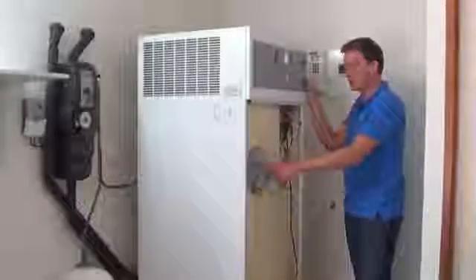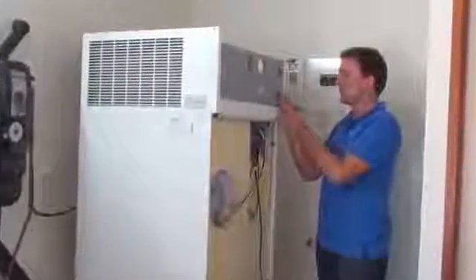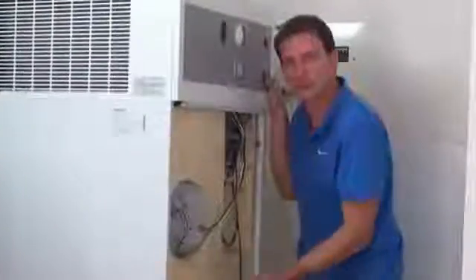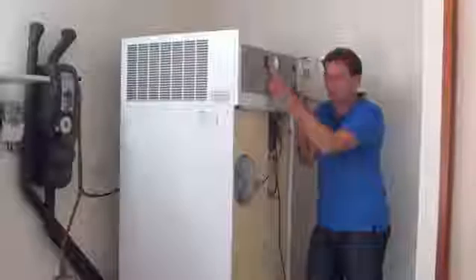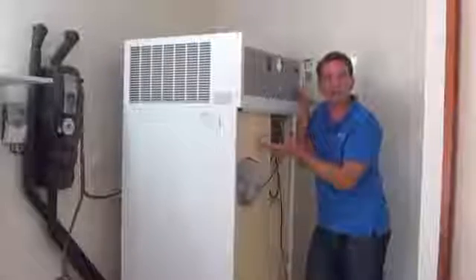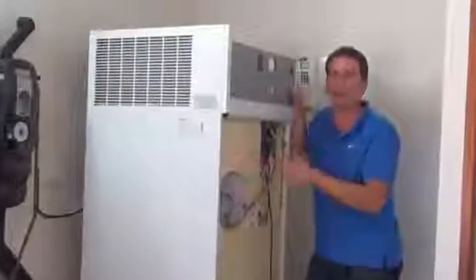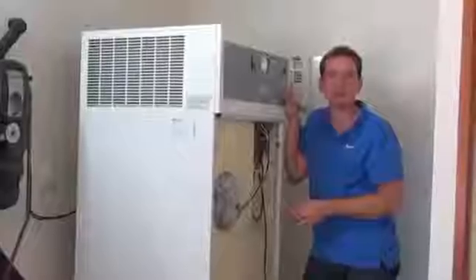Alright, just to show you quickly some other features that this heat pump has. Here we've got a switch that pushes the water in the tank up to 60 degrees. It actually switches on an electric element over here. We push the water above the normal 55 degrees that the heat pump generates. By doing that, you kill off all the Legionnaires and the E. coli bacteria that grows inside hot water systems over time. You have to push this temperature up, say, once every 2 months to kill off the bacteria.